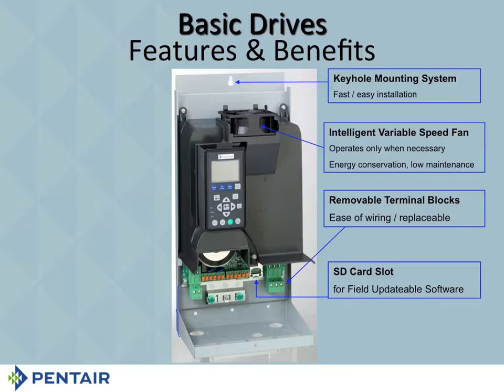Yes, I will admit we've had to use it in the past. When we very, very first came out with the drive, we had a little bit of a problem with something that didn't get programmed quite right. So we put it on the SD card slot and said, here, go plug it in. People went and plugged it in and everything was fine. It fixed itself. So that's what that SD card slot is for. Updates that give you a brand new drive without having to pay for anything.